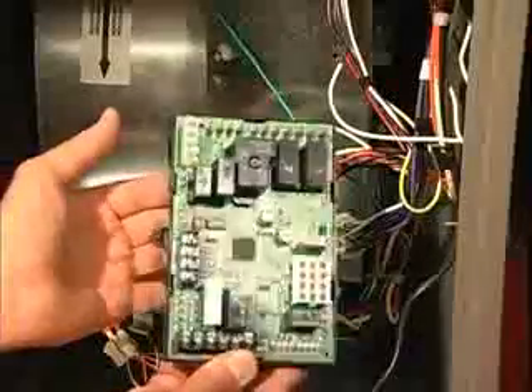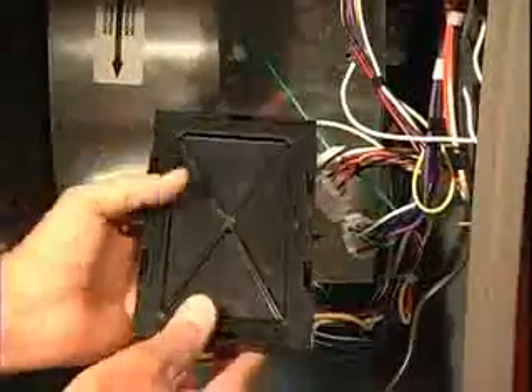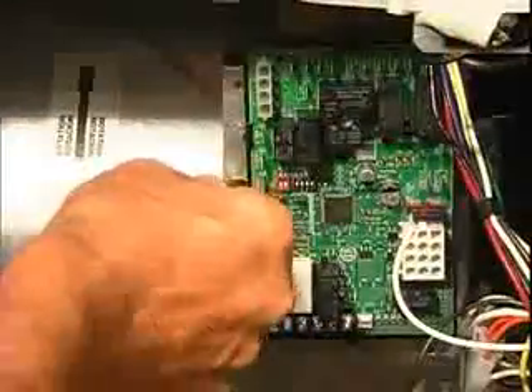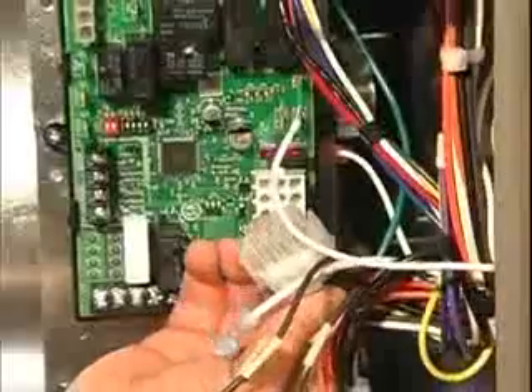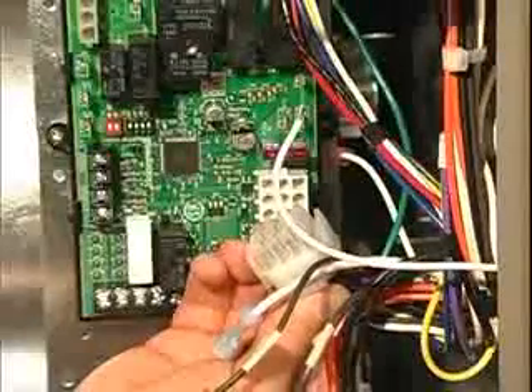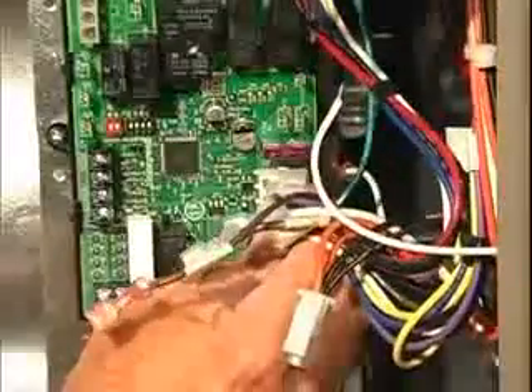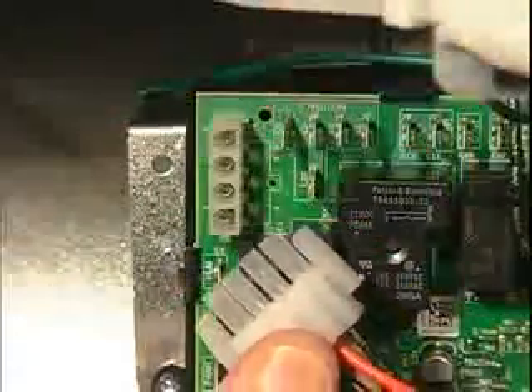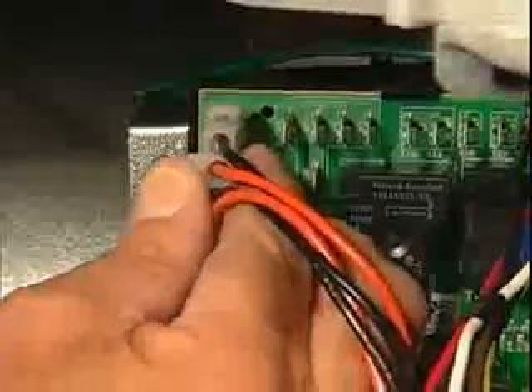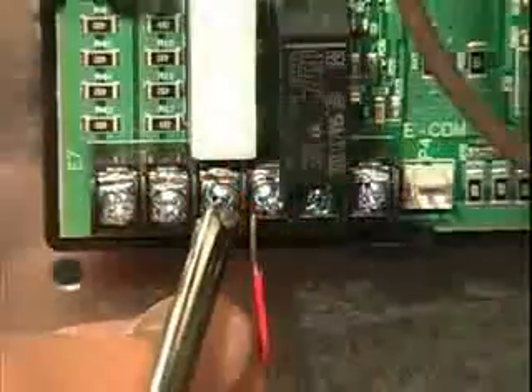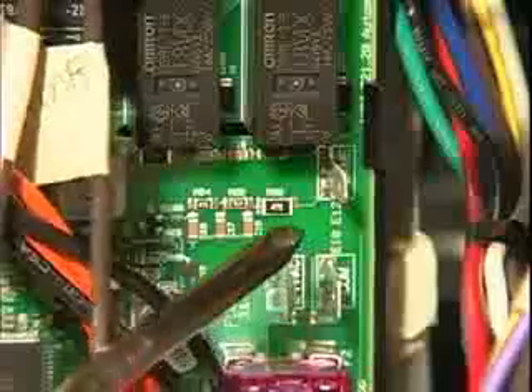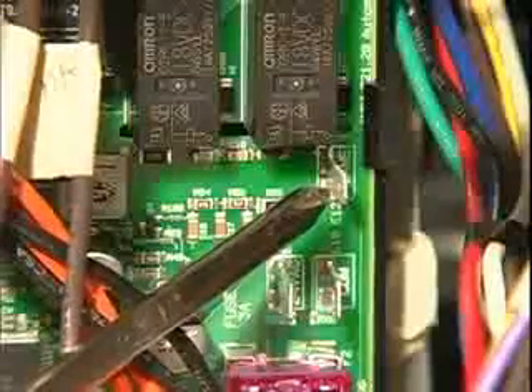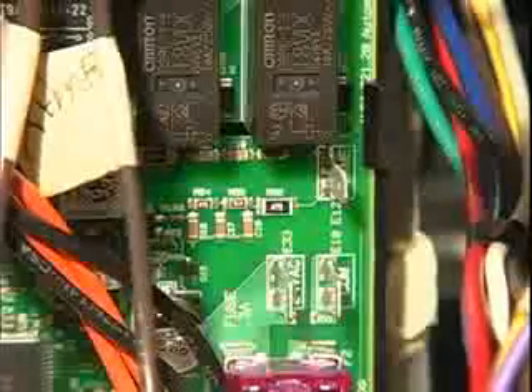In order to avoid bending or twisting force on the circuit board, it comes installed with a plastic mounting tray. Now you can mount the control in the blower compartment where the old control was. Here's the special harness for this furnace that connects the old plug to the new board, so we end up with a relatively simple plug-in wiring job. The draft inducer motor and the igniter are both line voltage loads that connect using this plug. The thermostat wires connect to traditional screw terminals. Finally, the lead from the flame detector hooks up right here. This is an optional connection for the flame detector. On this furnace, the flame detector lead goes to the 12-pin plug.